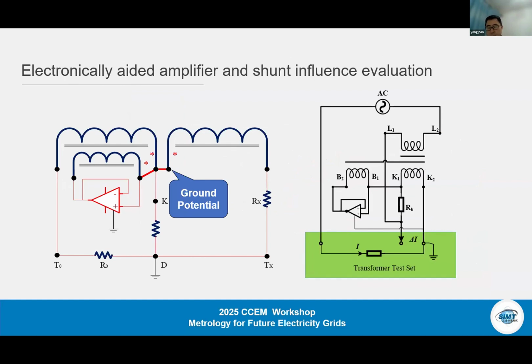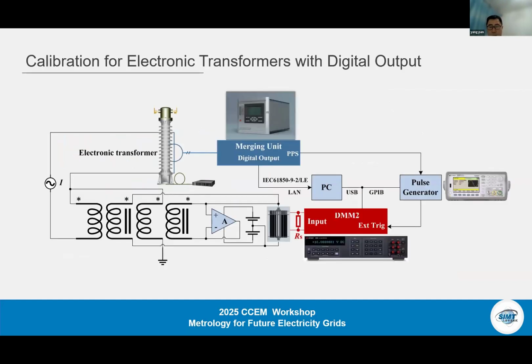So the reference two-stage transformer, aided with a voltage follower, is applied to minimize the inner magnetic flux, and the inner burden voltage of the secondary winding is removed. However, the capacitive error of the ratio winding, caused by the ground potential problem, needs to be evaluated. This is realized by self-calibration with burden shunts. So when calibrating electronic instrument transformers, the output of the ECT or EVT is presented as a set of time coherent digital data streams. This inherently necessitates a new reference system for accurate calibration.